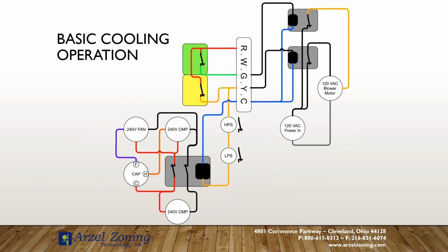On a cooling call though, and this goes way back, it's been like this for a very long time, a cooling call always has to have a fan call with it, because your cooling call, the Y, really only controls your compressor, and it determines whether or not the furnace needs to run a high speed or a low speed blower, but it does not determine that the blower actually operates. Your G call still needs to be there. And with the RSL panel, if the G call is not there, the panel will view it as an illegal call. So if you are missing G, you don't have a valid call for cooling. A valid call for cooling is Y and G.